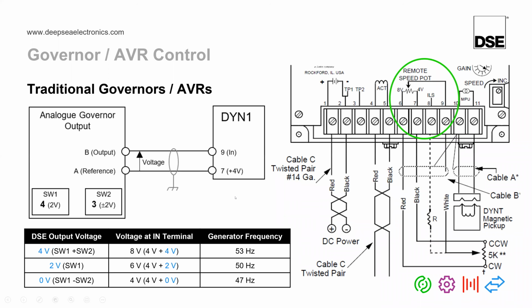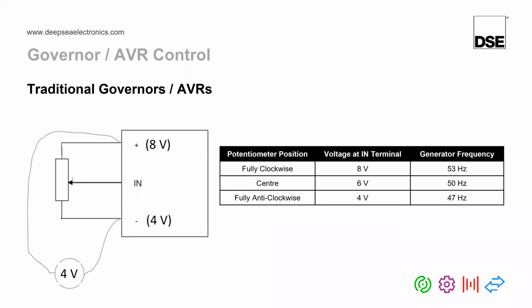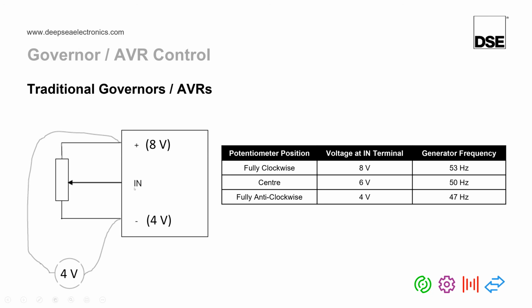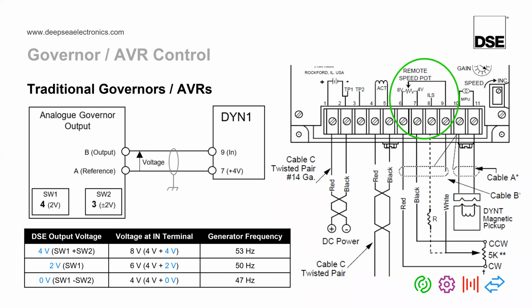And these relate to the terminals on the governor itself, which you can see from the wiring diagram here, is terminal 7, 4 volts, and 9, which is effectively the in terminal, or the wiper of the potentiometer. Again, going back to the previous slide, you can see that the wiper of the potentiometer is going to the in terminal. So the way the DSE module works in terms of its wiring, as you can see here on the left-hand side, we have no external potentiometer connected. Instead, of the 3 terminals, we're only connecting to 2 of them.